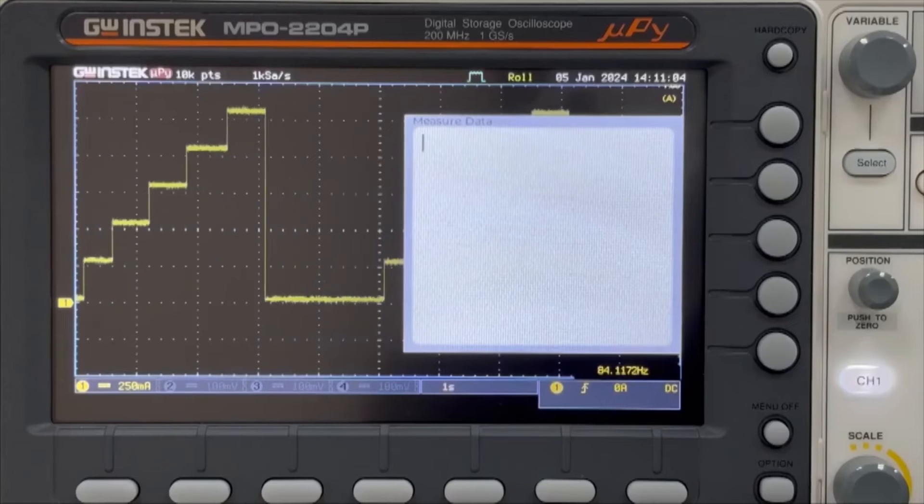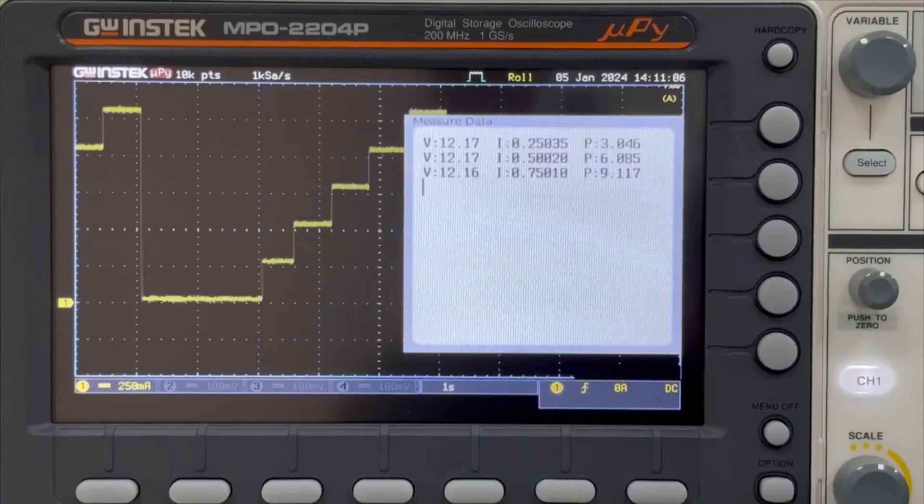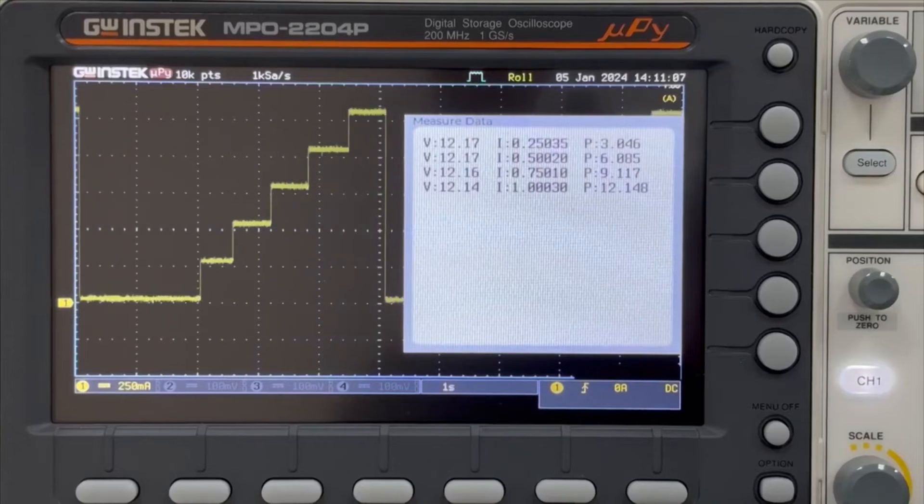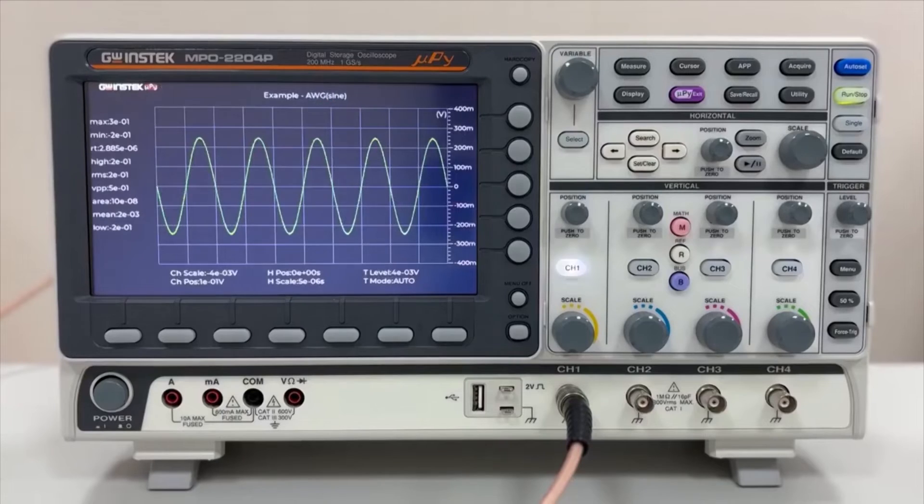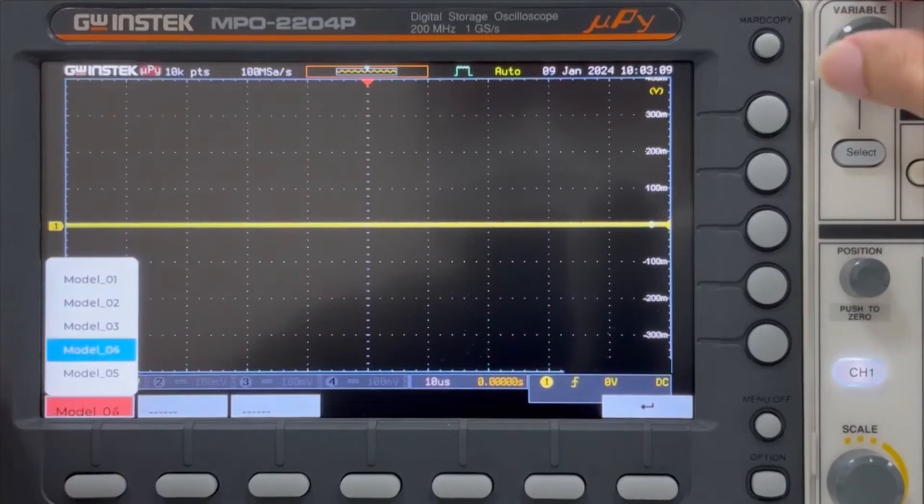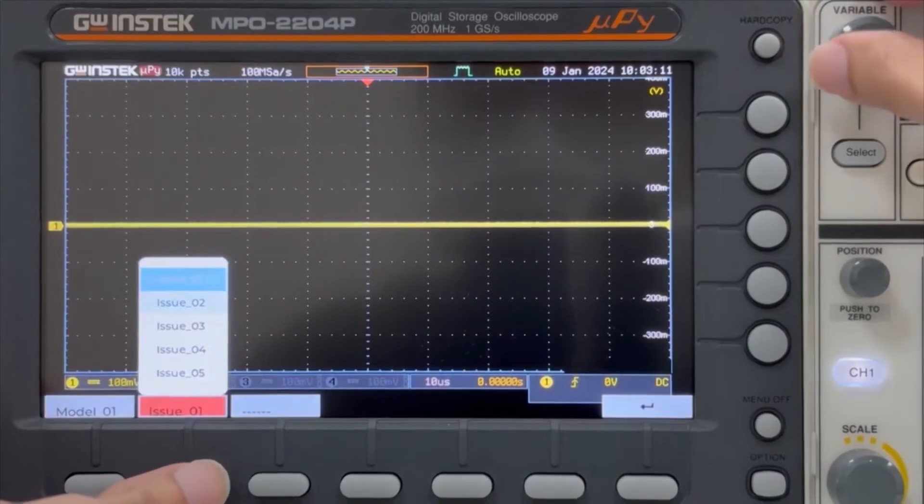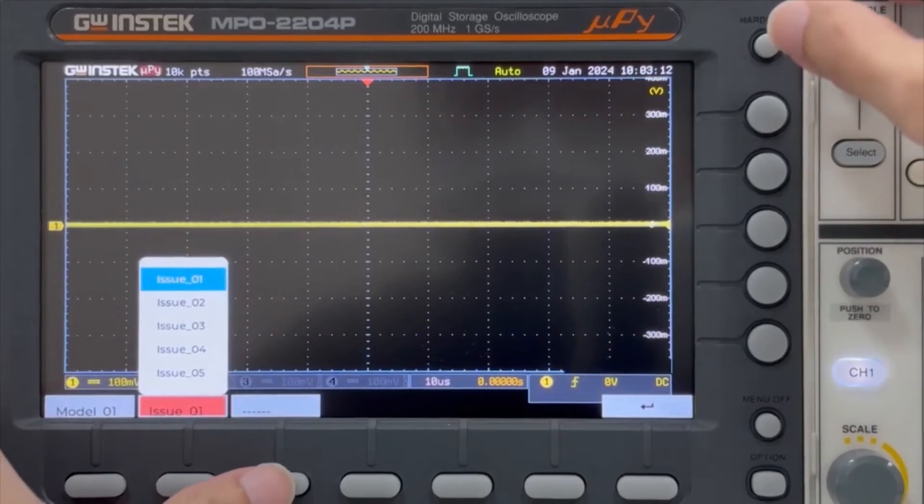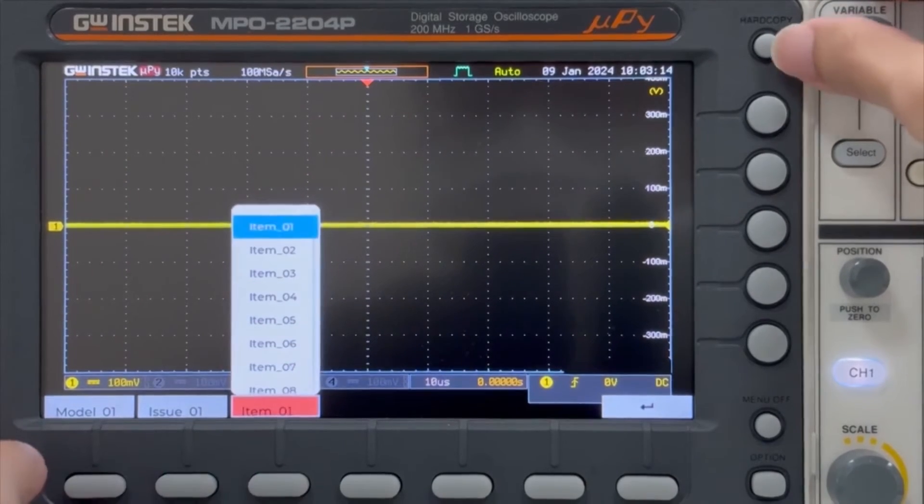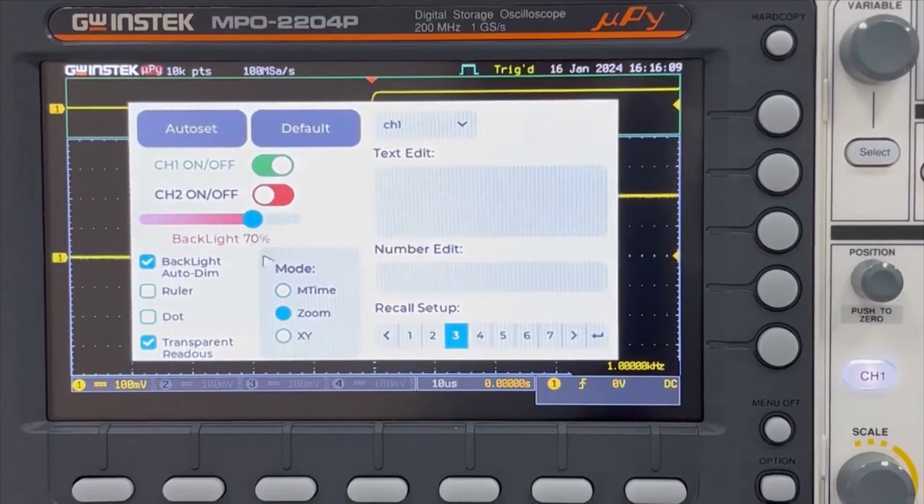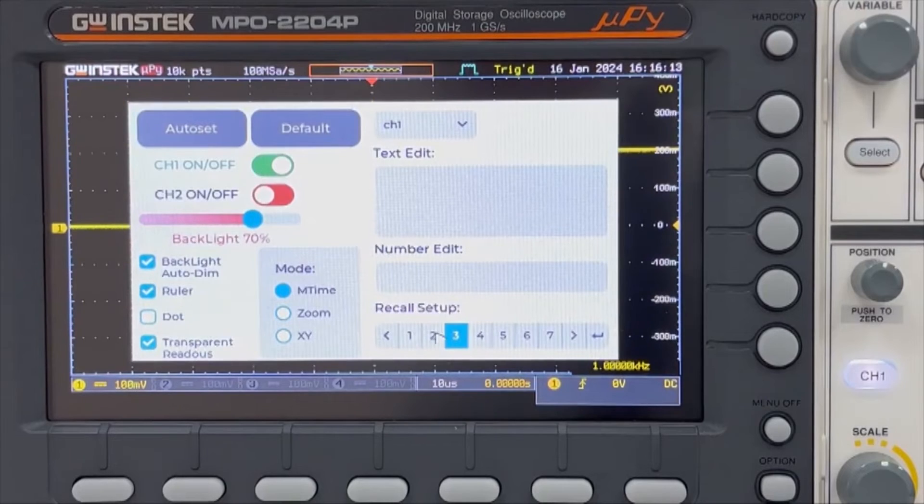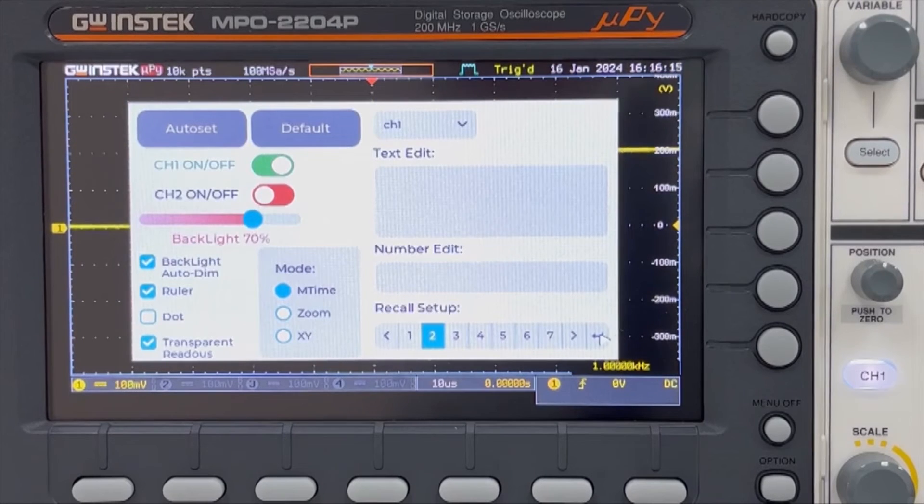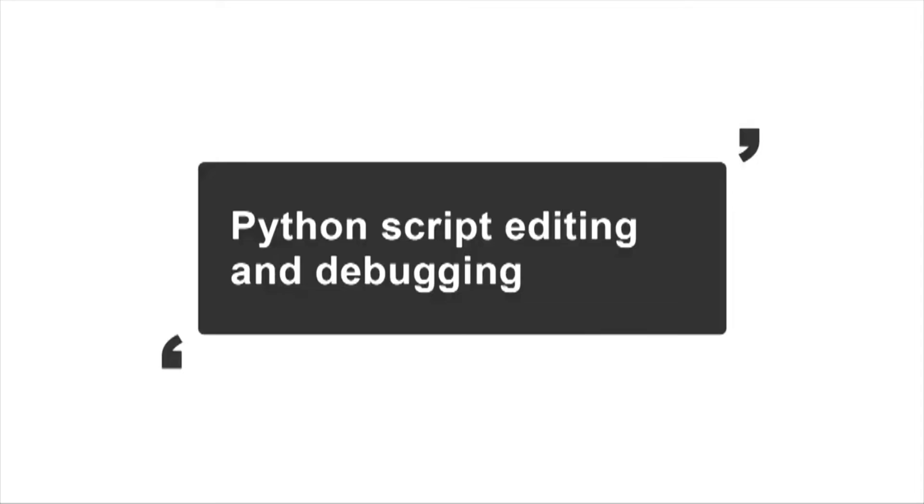MPO-2000 provides a GUI library, allowing professional version users to invoke the library in Python scripts to draw waveforms and charts. This capability enables the creation of user-defined menu screens and custom measurement functions directly on the MPO's LCD screen. The plotting library includes various widgets that Python scripts can call.